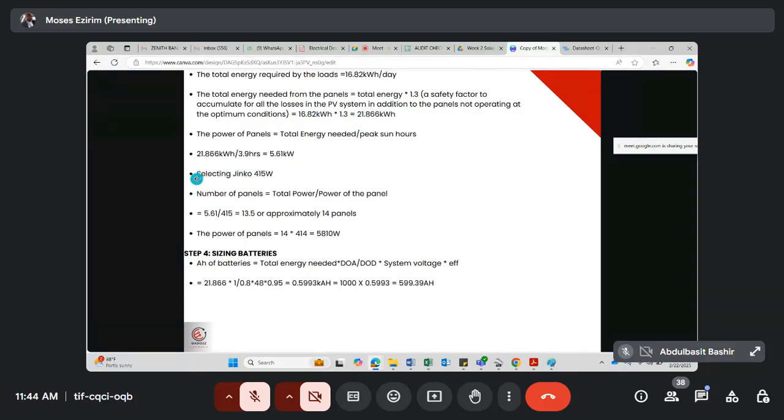I'm sure you can still remember how we divided the energy that we got from the utility bill. 150,000 divided by, exactly, the peak sun hour. That's the PV potential, which can also be called peak sun hour. But in this case, I have to factor in tolerance, just in case. So you can see now I'm dividing it by the peak sun hour, so I have this to be my capacity.